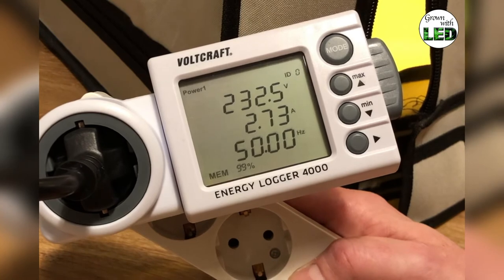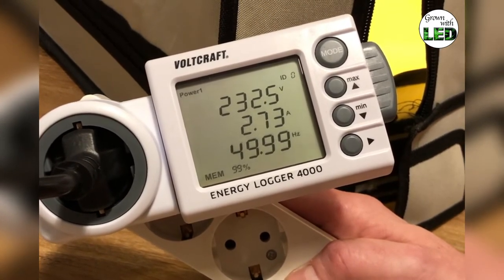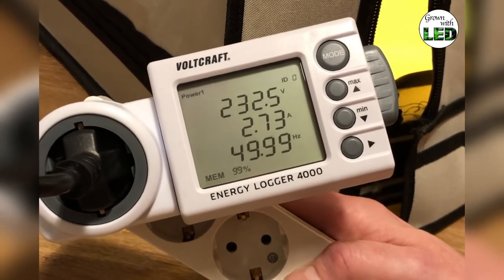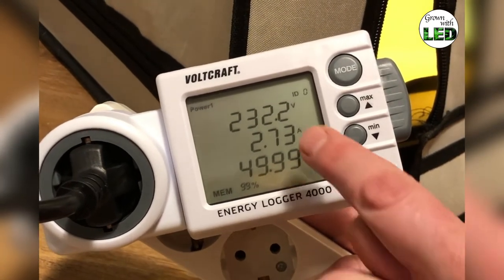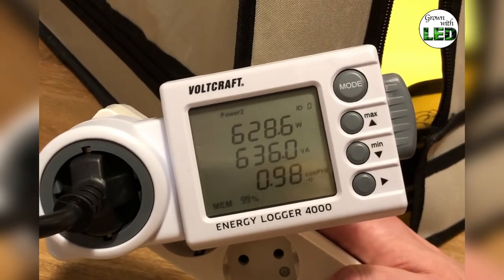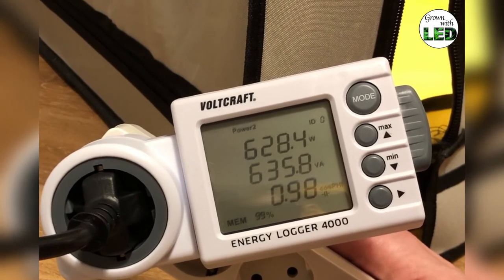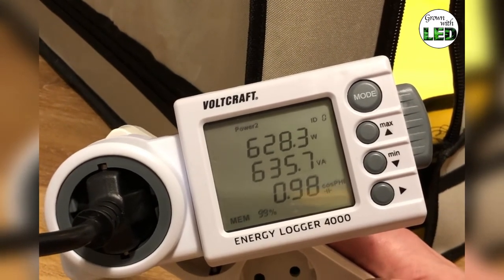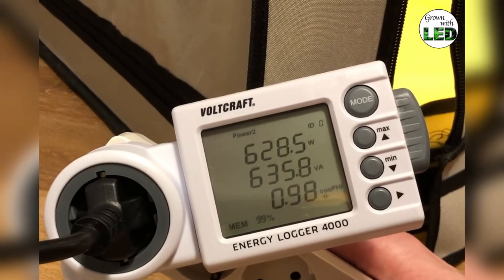Here we have the Voltcraft Energy Logger 4000 measuring the HPS 600 watt right now with the Lumatek ballast set to the 600 watt setting. At this moment we have 232 volts, drawing a current of 2.73 amps. Pushing the mode button, we can see this is using 628.5 watts, or 635.7 volt-amperes, with a power factor of 0.98. Those are the measurements for the standard settings of the ballast.